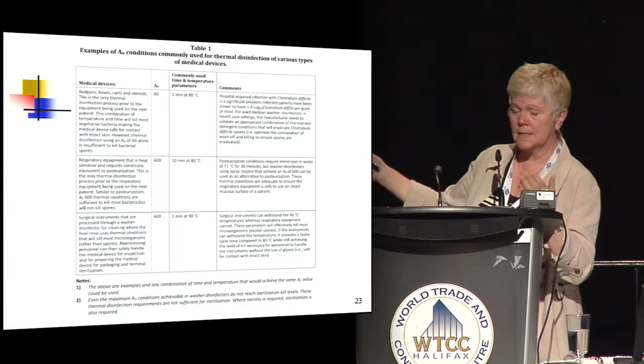So looking at this table now, I'm only showing it as an example to indicate to you, this is a copy of a page from the CSA guideline, and the examples that are given are an A sub naught of 60, an A sub naught of 600, and so on. And there are examples of the time frames, so 1 minute at 80 degrees gives you an A sub naught of 60. And you can think about that. That is the thermal disinfection parameters that are in your washer disinfectors. And that's what's making, for instance, your instruments safe to handle after they've gone through the washer disinfector.